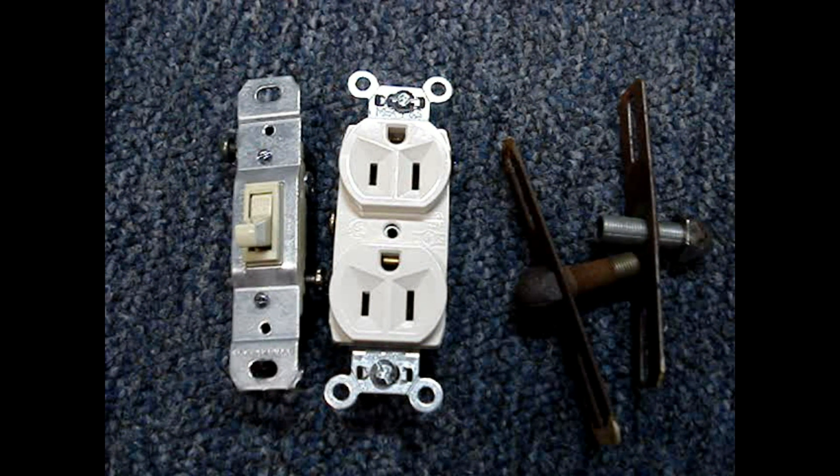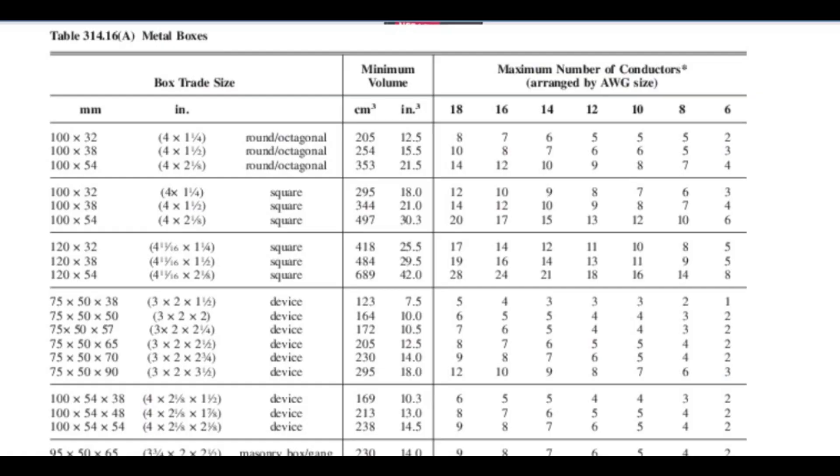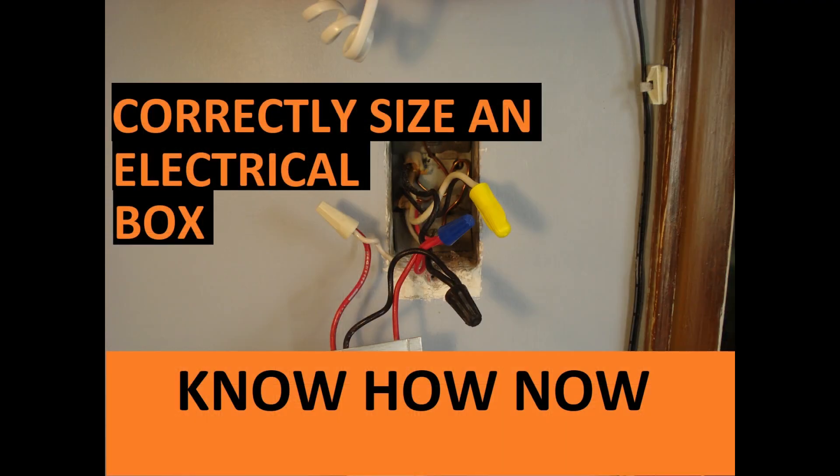If the box will not contain any internal clamps, devices such as switches or receptacles, or fittings for light fixtures, two tables and a few simple rules from the code can be used to determine the maximum amount of wires allowed in a box. Calculating the volume used in a box containing receptacles, switches, or light fixtures is more complicated. To find a video that discusses that topic, click on the channel name KnowHowNow and look for a video titled 'How Many Wires in a Box?